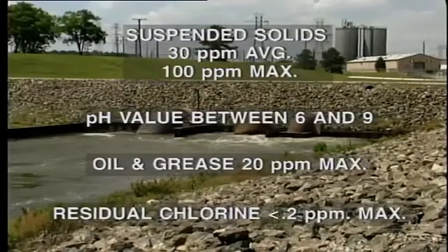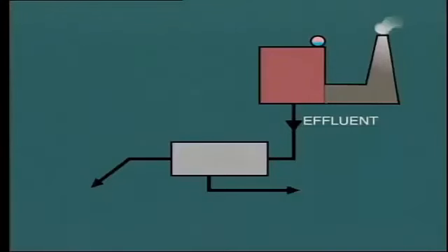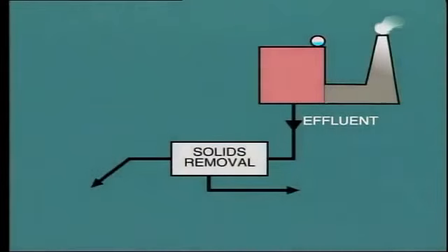In order to comply with these limits, it is necessary to remove offending solid material from the effluent, and this is done usually by clarification and/or filtration. Most of the solid material is removed and must in turn be buried in a certified landfill site. Before the final clean effluent is discharged into the river or lake, the pH will be corrected by the addition of caustic or acid.